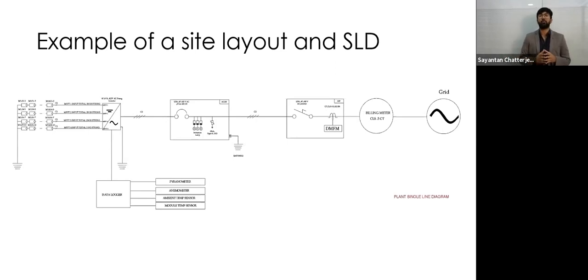And before that, in most cases where your inverter and ACDB are, the grid interfacing panel is somewhere else. So we provide a grid interfacing panel which also has an MFM meter so that we can see the energy and all this. And there is an isolation, like on a smaller scale it's an MCCB, on a higher scale it will be a breaker.